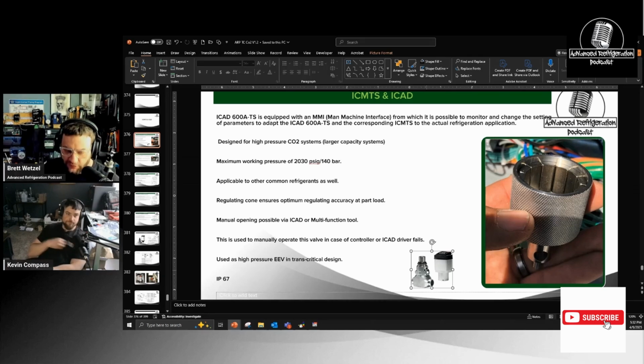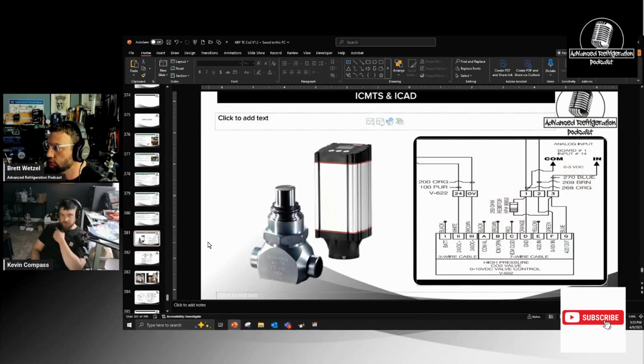I also realized that the bottom portion here, the actual threaded portion, is actually for the valve. So the seat of this valve, one of my buddies actually had one where the seat was actually loose upon startup. So the valve was saying that it was at 100%. It was in fact at 100%, and I told him to pull it apart after he had the gasket or whatever, and he didn't. But needless to say, he did that, and the seat from startup was actually loose. I've had that a lot on the CCM valves. I've had the seat be loose a lot in the CCM valves.